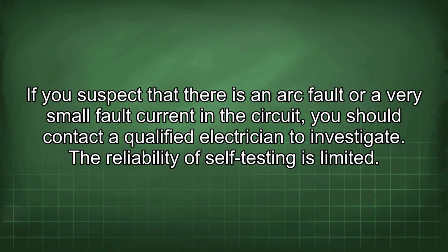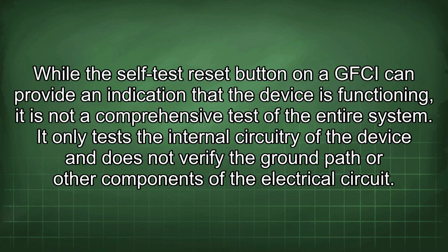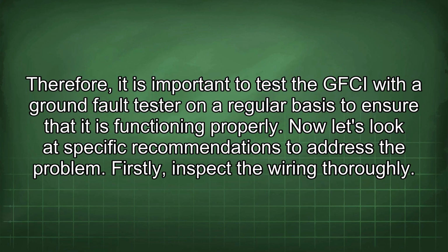The reliability of self-testing is limited. While the self-test reset button on a GFCI can provide an indication that the device is functioning, it is not a comprehensive test of the entire system. It only tests the internal circuitry of the device and does not verify the ground path or other components of the electrical circuit. Therefore, it is important to test the GFCI with a ground fault tester on a regular basis to ensure that it is functioning properly.